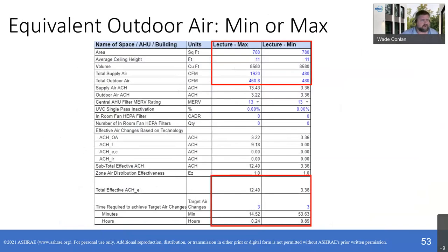One of the things that we really want to stress is that if you've got VAV systems, you've got a max and a min, and where does your system really operate? So this is a lecture hall at a university. I put in the information that I had from the boxes, and you can see at minimum, essentially, it's 100% outside air. At maximum, it's almost 2000 CFM. As you come down to the bottom, you can see that at maximum, I'm doing 12 and a half air changes. At minimum, I'm doing 3 air changes. That minimum is minimum cooling. If you're heating at 60% of cooling max, you might be at a much lower number.